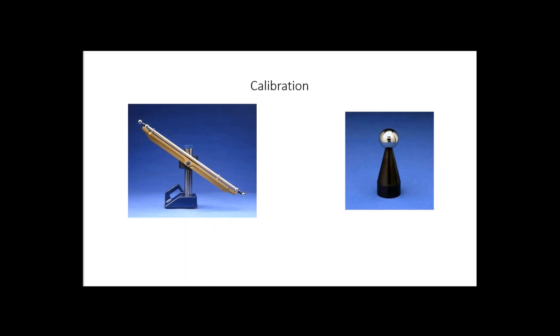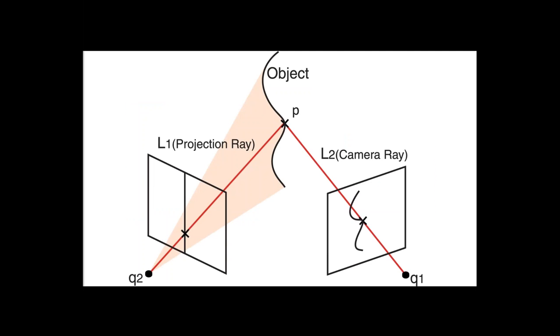Some systems will have multiple calibrations. A lot of the laser scanners do. One for the laser scanner and another for the locating device, such as the arm or laser tracker. The proper calibration is going to ensure that the laser or the camera is properly detecting the projected light, and the system is placing that collected data in the correct XYZ location.